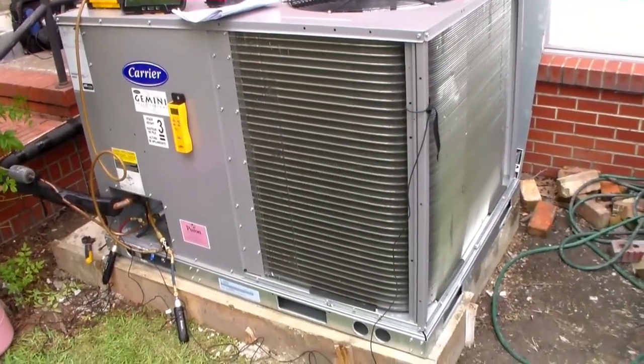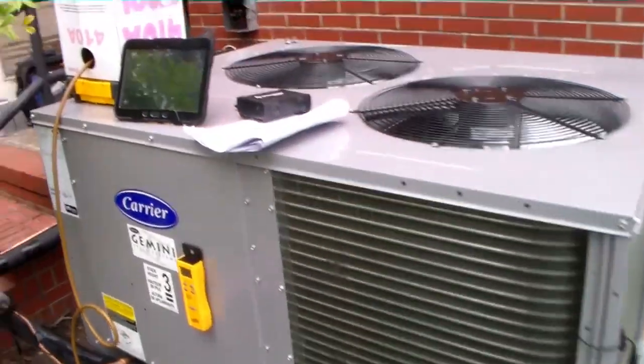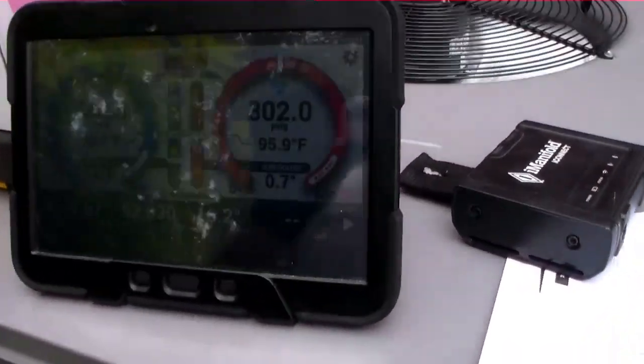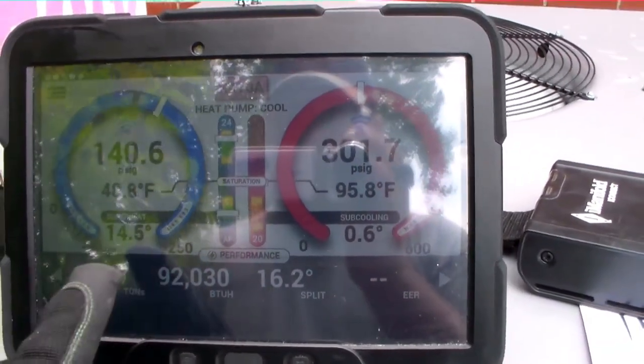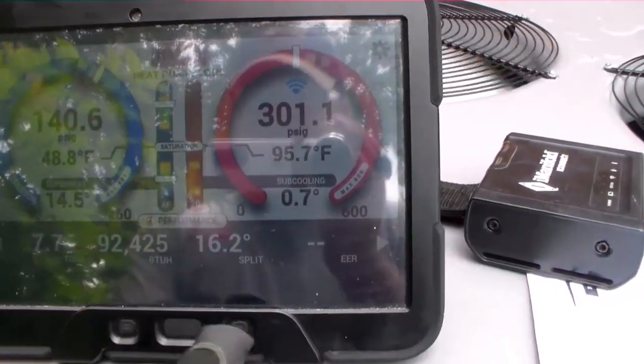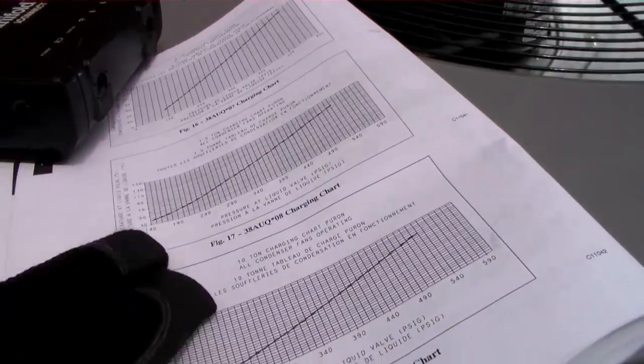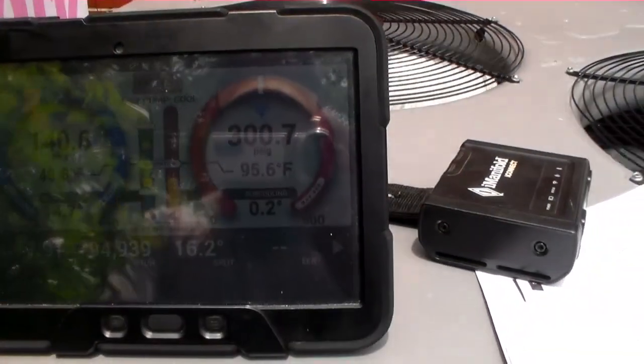Guys, we have our unit running here. It's been running for probably about a half an hour or so. We're still charging it up. See, we have a good superheat. We have very little subcooling. Going by the equipment charging chart I have here, which just ensures we have some subcooling. We are still lacking charge a little bit. We're going to keep on charging it up.